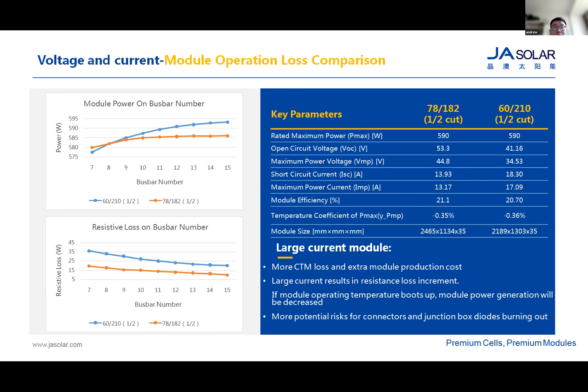This is the value we analyzed under the GE R&D Center. We set up a test bed for comparison between the 182mm module and the large current module. The real data was collected based on one intraday solar system operation, and you can see that solar module temperature becomes higher when module current is higher, leading to significantly reduced power generation.